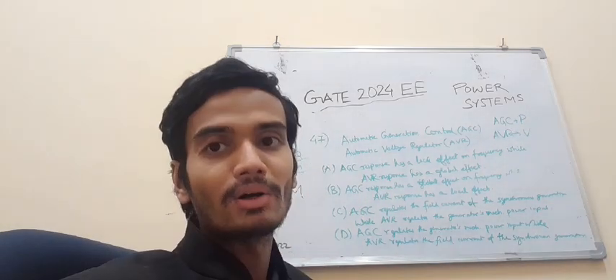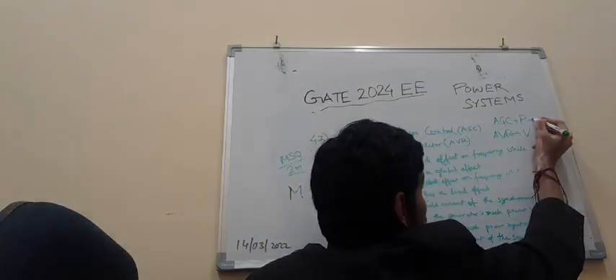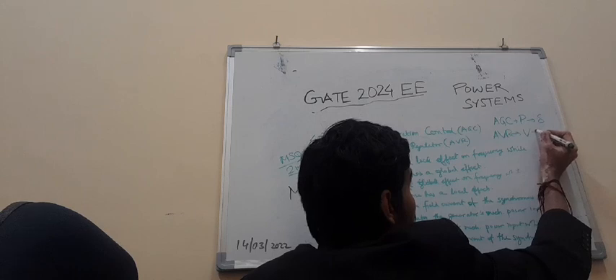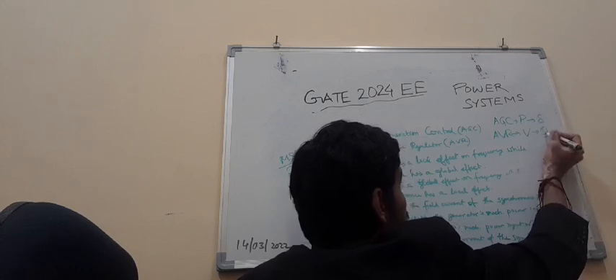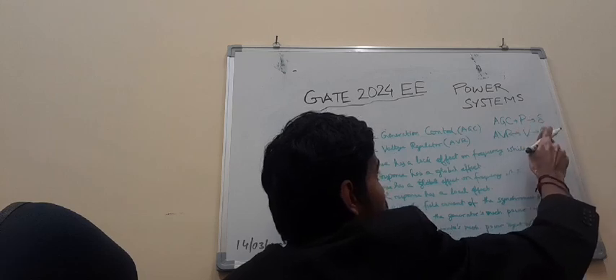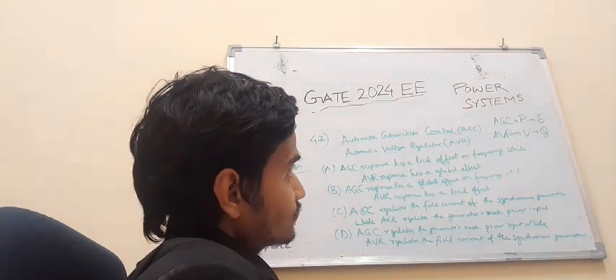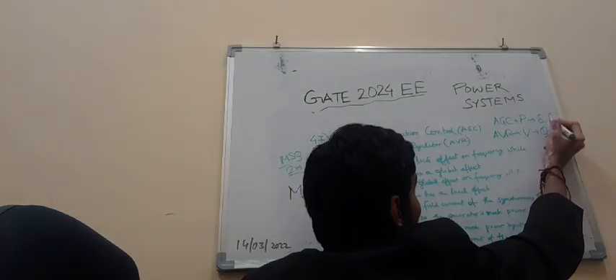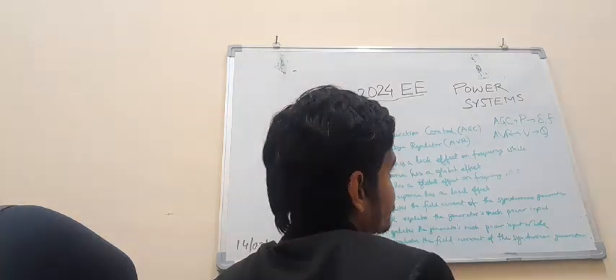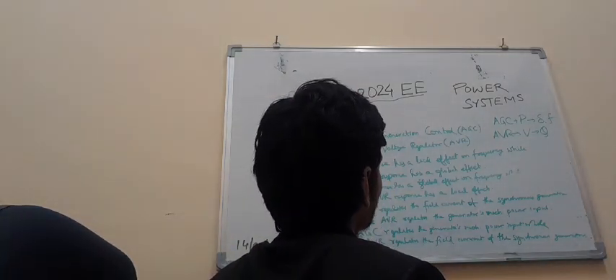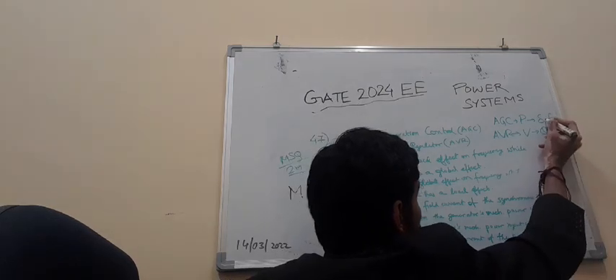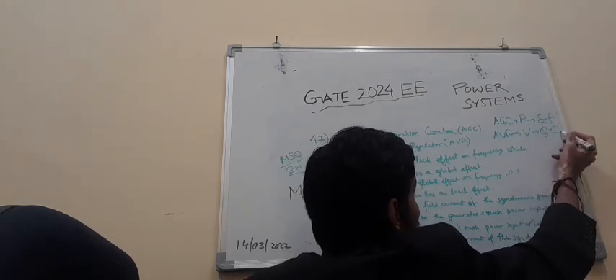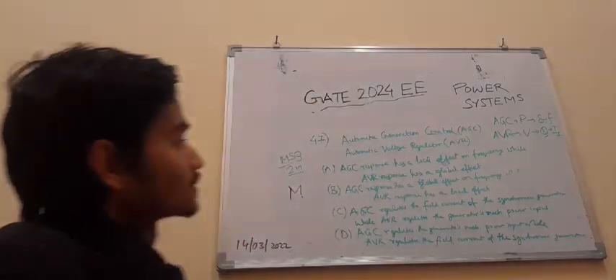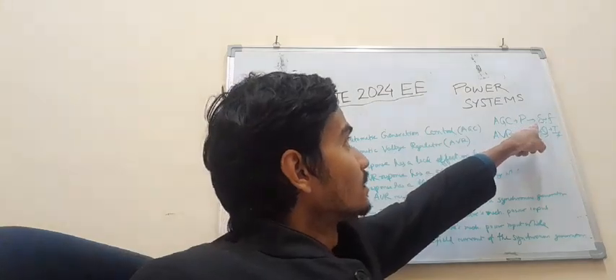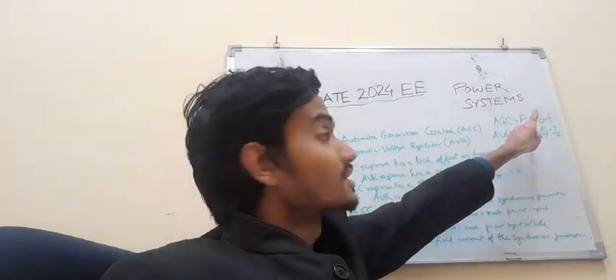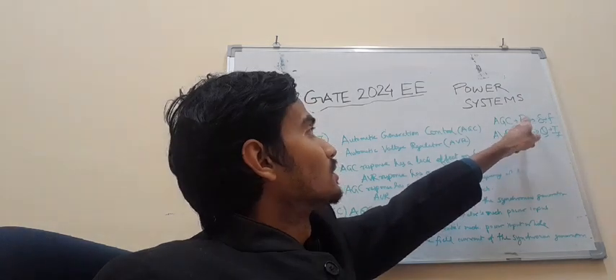Now in a power system, for high voltage power systems, we know that P is strongly coupled to delta and Q is strongly coupled to V, right? And F also. And Q, how can it be controlled? By regulating the field current. So P is strongly coupled to delta and hence related to frequency control, real power output.